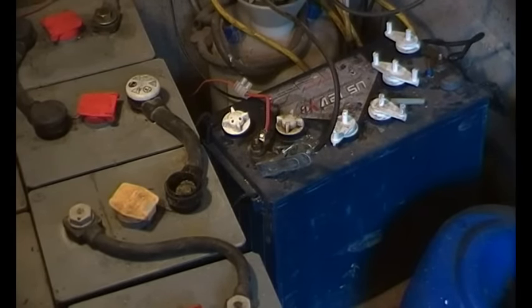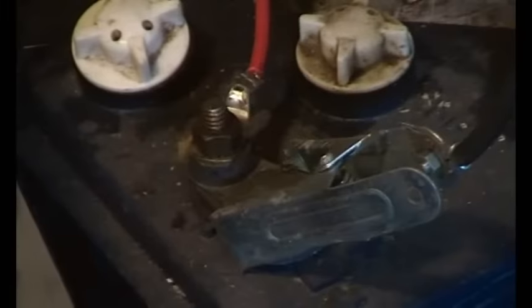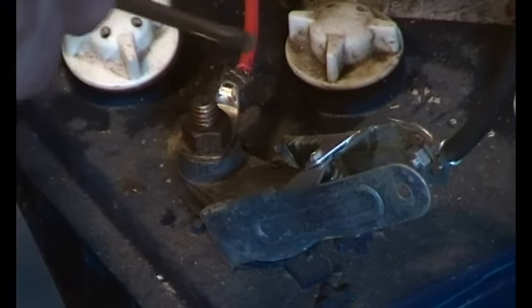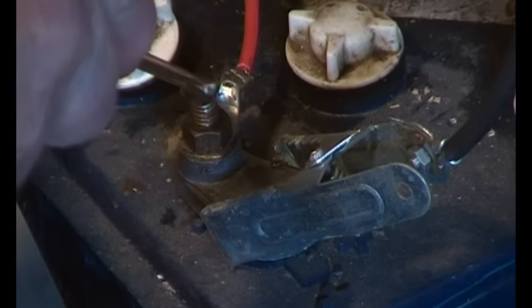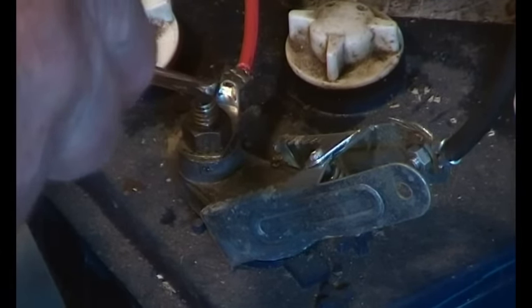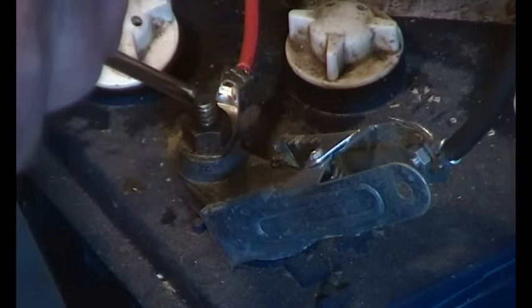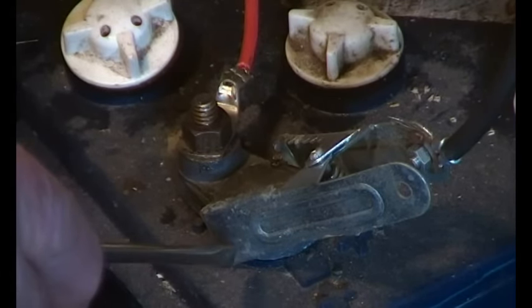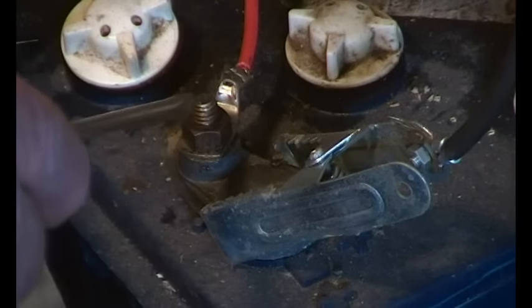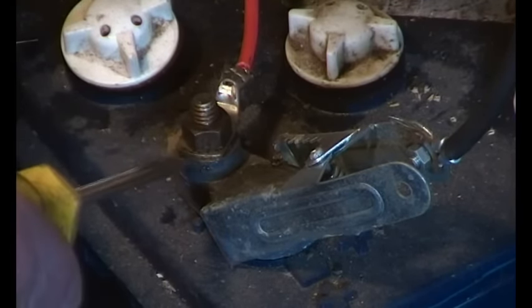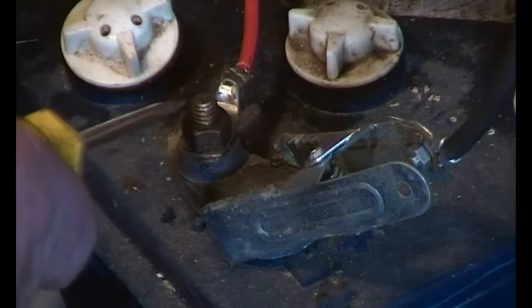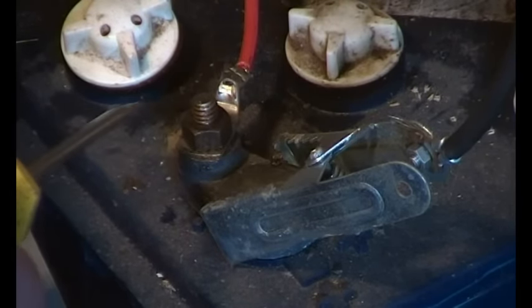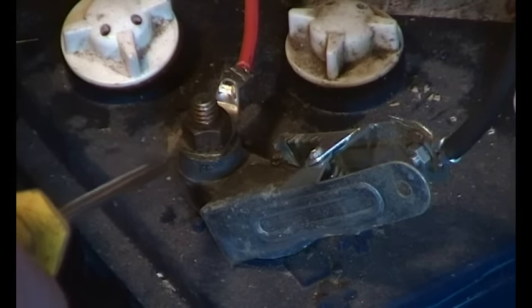There's just an interesting bit here on the slave battery. This is the positive terminal. This red wire comes from the main battery pack through a light bulb as a resistance that cuts down the current and therefore pulls the voltage down. Now if we were to put this, which is the feed to the trackers and some of the charge controllers, on there, then if there was a duff connection down here we could get 48 volts or even up to 60 volts going straight to the charge controllers and the timers, which would do them no end of mischief.